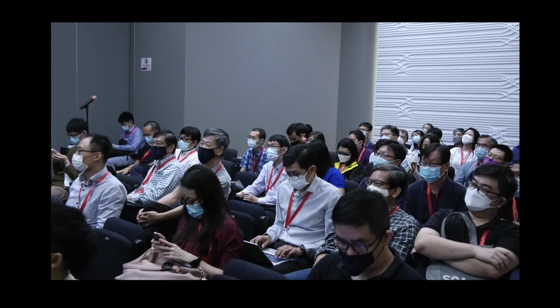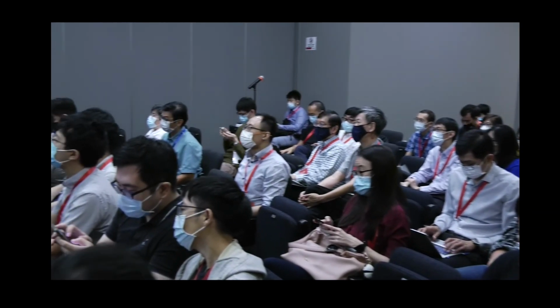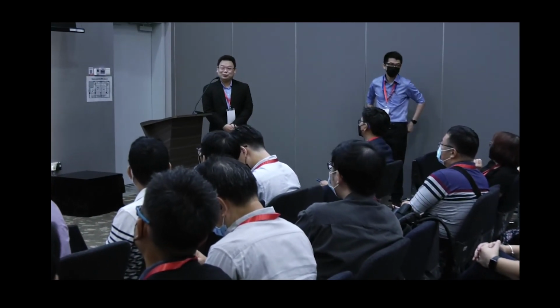Sorry. How long would you expect area A to sustain more than 35.5 degrees at any time? Actually, none, as much as possible. The moment it hits 35.5, the exhaust system will kick in and the temperature will start dropping. The exhaust system will start pushing out the hot air and pulling in cold air from outside. Whenever the exhaust system turns on, it stays at 35.5 for a very short period, maybe less than a minute, and you start seeing a drop.